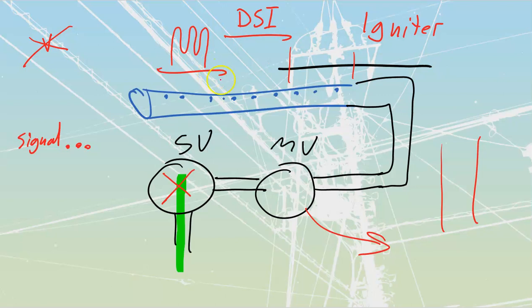So let's start by taking a look at direct spark ignition, where I'm going to have two probes that go across. Or in a lot of cases, what's actually happening is we're going to have grounded metal attached to my manifold, and then the actual spark probe itself, which is going to look almost like an unbent spark plug from a vehicle. We're going to have a cable. It's usually really flexible, kind of like your meter leads, that really, really soft silicone rubber type, because it's used for high voltage. It's going to be running a high voltage conductor through the middle there.